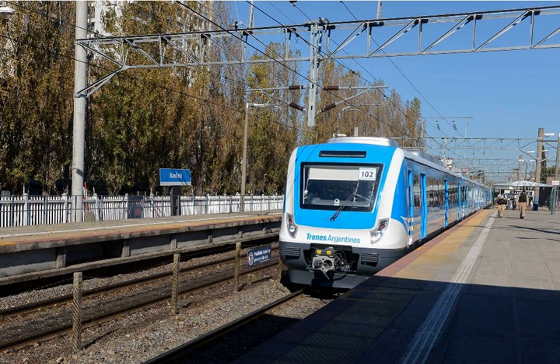Railway electrification using 25 kV 50 Hz AC has become an international standard. There are two main standards that define the voltages of the system: EN50163-2004 plus A1-2007, Railway applications, Supply voltages of traction systems; and IEC 60850, Railway applications, Supply voltages of traction systems. The permissible range of voltages allowed takes into account the number of trains drawing current and their distance from the substation. This system is now part of the European Union's Trans-European Railway Interoperability Standards, including EC Interoperability of the Trans-European High-Speed Rail System and EC Interoperability of the Trans-European Conventional Rail System.